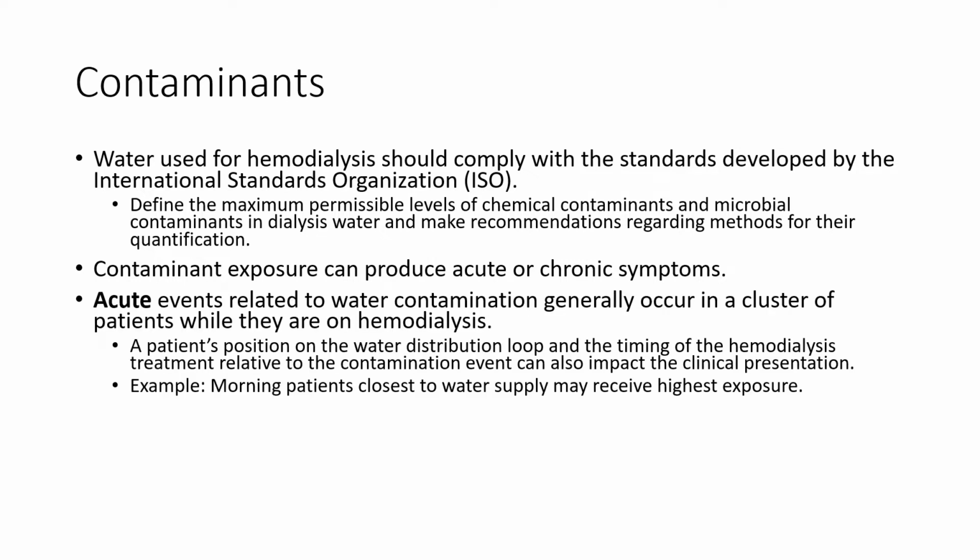Acute events related to water contamination generally occur in a cluster of patients while they are on hemodialysis. Although, remember that the severity of these events and their onset during a dialysis session can vary between patients. As an example, exposure to residual disinfectant in the water supply loop predominantly affects patients who are most proximal to the water supply during the first treatment session following disinfection, so like the morning patients.